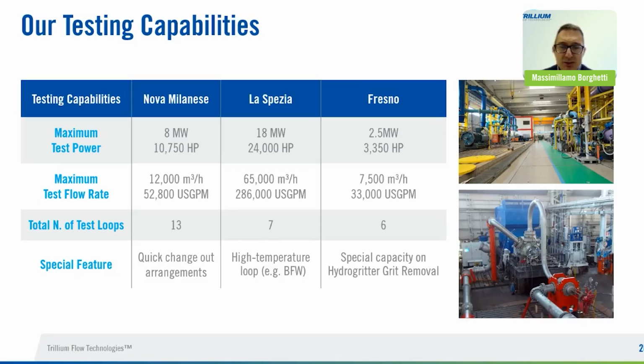Now we move to La Spezia, where the maximum test power is increased up to 18 megawatt, and also the maximum flow rate up to 65,000 cubic meter per hour. The special feature is the capability to test a large pump in full scale, and also the possibility to run, for example, a boiler feed pump at the plant temperature. Basically, we have a high temperature loop able to run up to 200 degrees C.